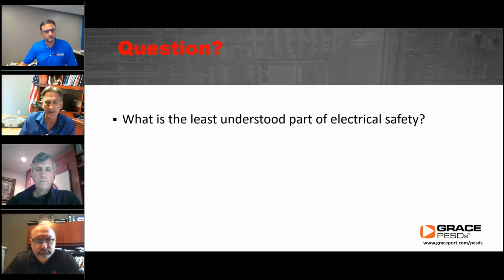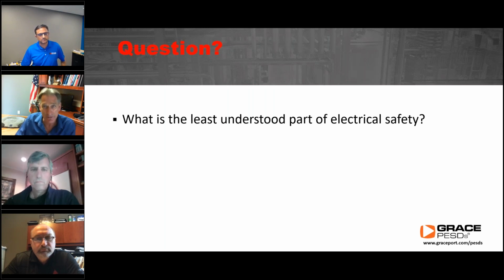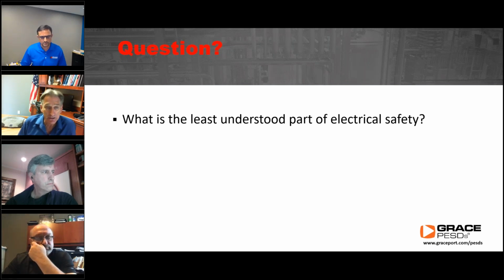That's one of the things a lot of people don't understand. Someone turns off the power, maybe even an external source into a cabinet, and there's a disconnect on the outside. They say, I've turned the power off, it's dead on the inside, so I'll open it up without wearing any PPE and test for absence of voltage. No, until you've established that the equipment is in an electrically safe work condition, which takes seven or eight steps, that equipment is energized. A lot of people don't get the concept that turning it off from the outside does not mean it's de-energized on the inside.